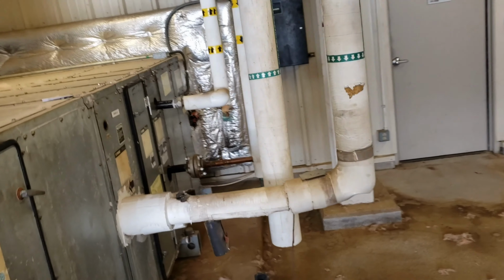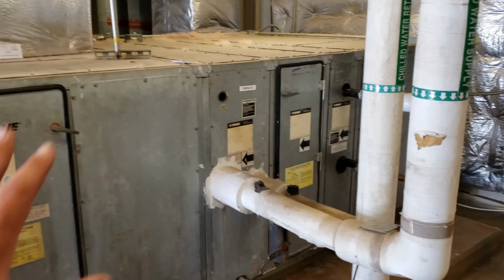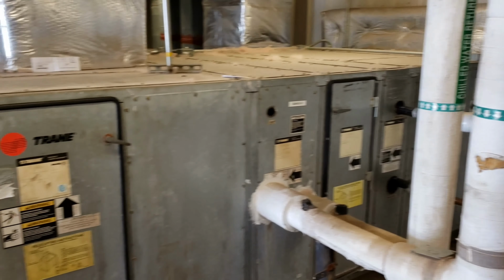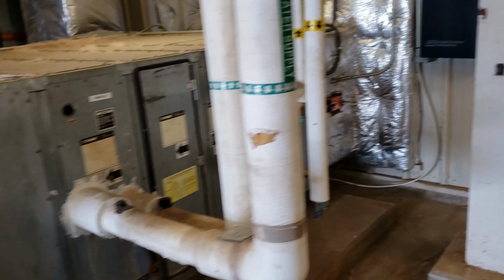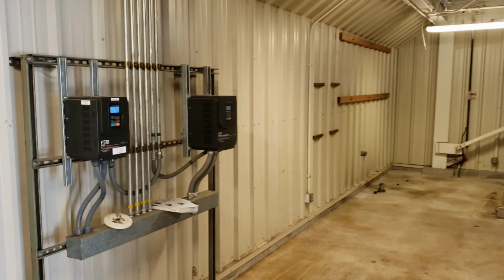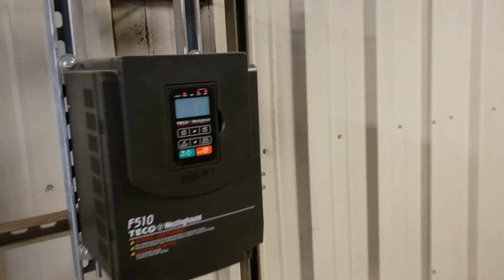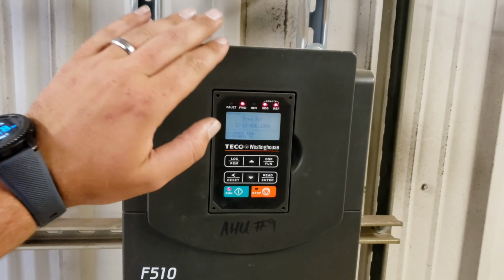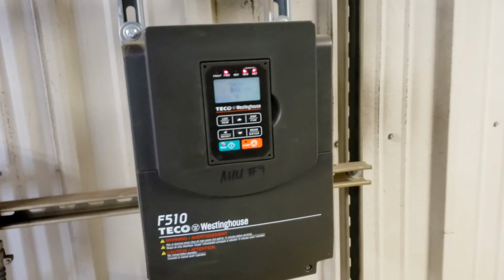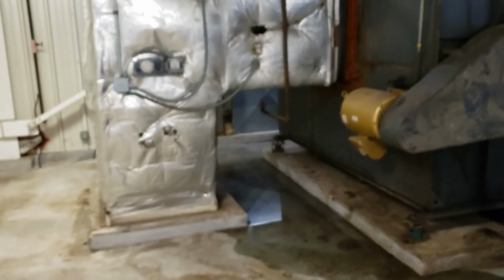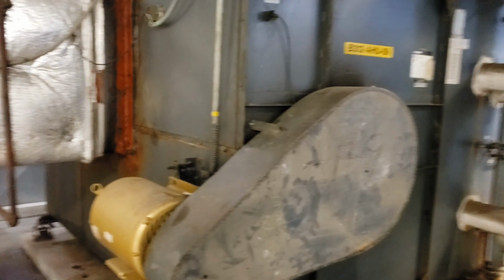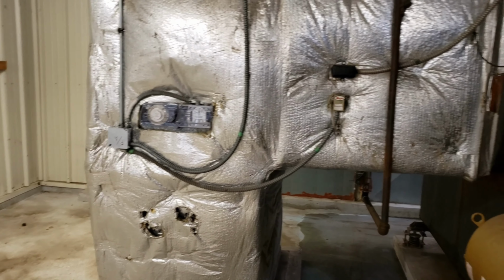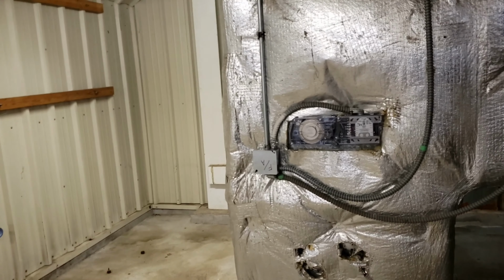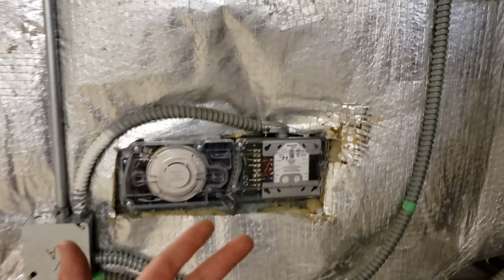This unit here, they weren't running. They just didn't have it on, and instead of getting it to turn on, they ended up condemning it. I got it functional, and so confirmed that there. And this VFD here was in hand, and because of the way it was wired, it allowed it to bypass the safety, which was preventing the air handler from shutting down, even though the fire tripped. So redid all of that, got it working properly now. Every time it loses the fire contacts, it kills the whole system.